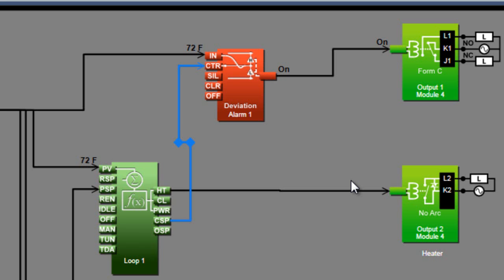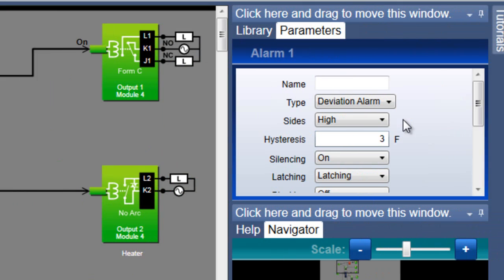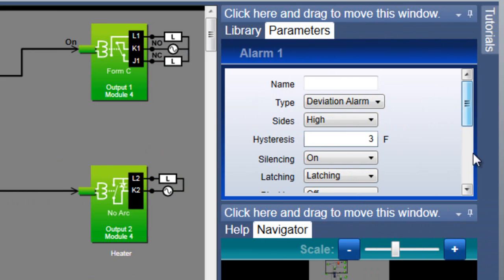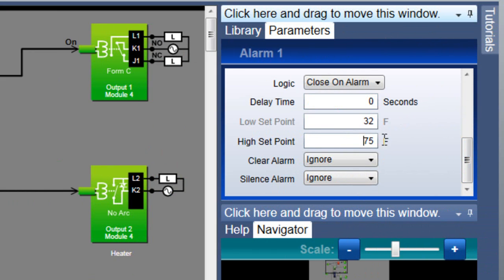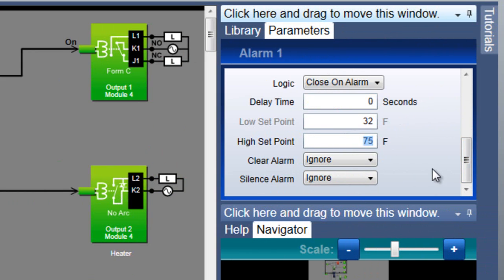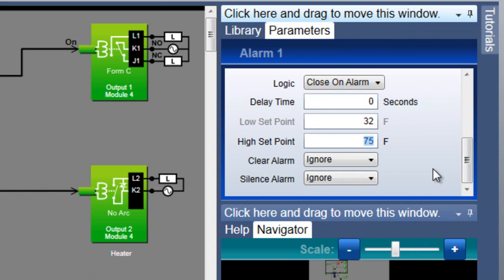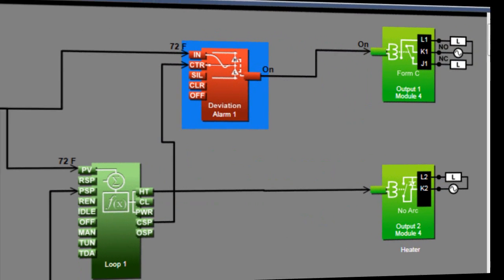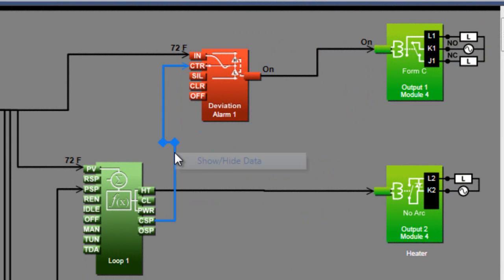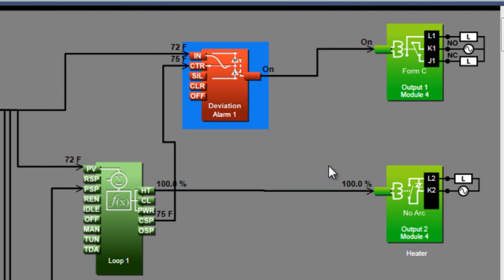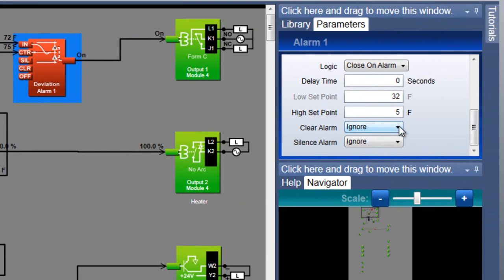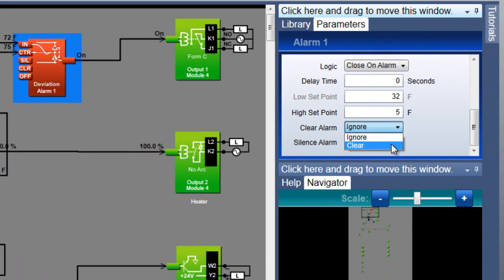Since for a deviation alarm, the alarm setpoints are relative to the loop setpoint, if I want the alarm to occur when the temperature is 5 degrees or more above the loop setpoint, I set the alarm's high setpoint to 5. If the loop's setpoint is 75, the alarm will occur at 80. It's convenient to tie the alarm to the loop setpoint in this way when you want to be notified if there's a deviation from setpoint.